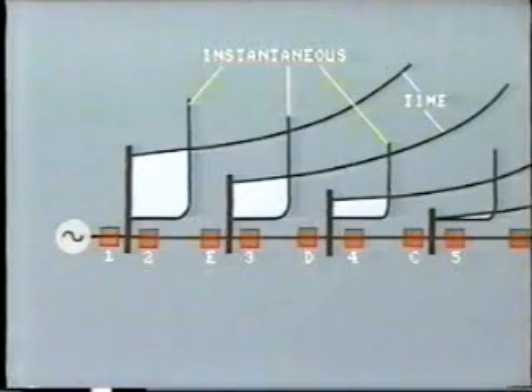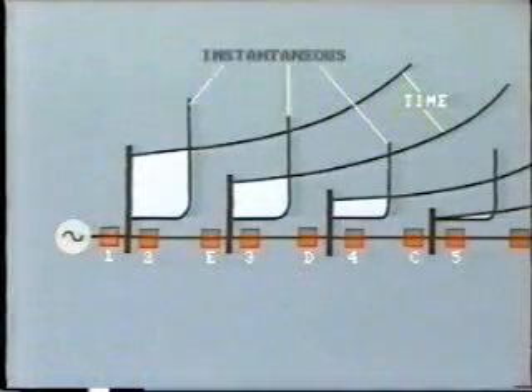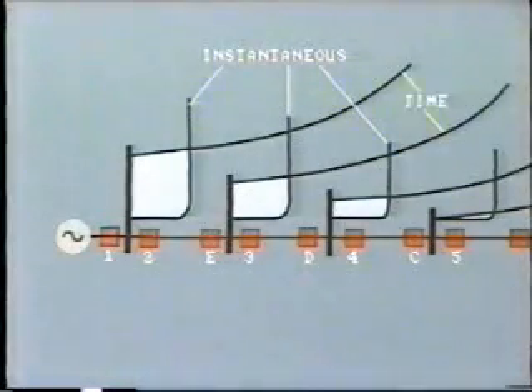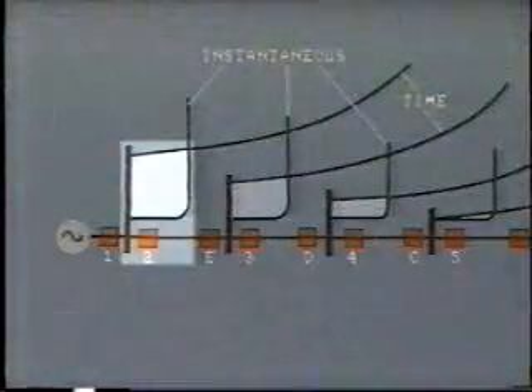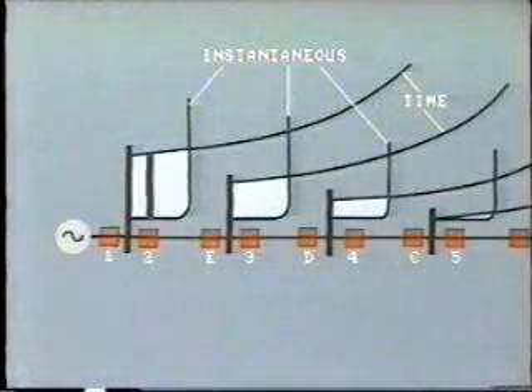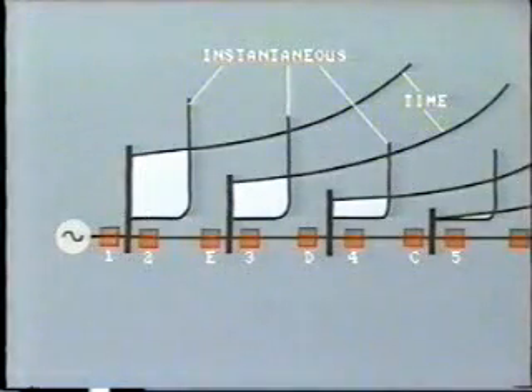Looking along the line, the set of coordination curves would look like this, where instantaneous overcurrent relays are installed in addition to time overcurrent relays. Clearly, the biggest improvement in relay operation is close in to the power source. The reduction in time for a fault at this location is significant. There is another incidental advantage.